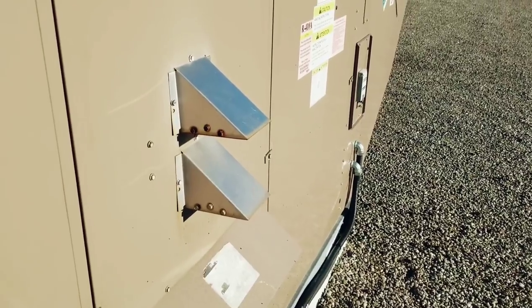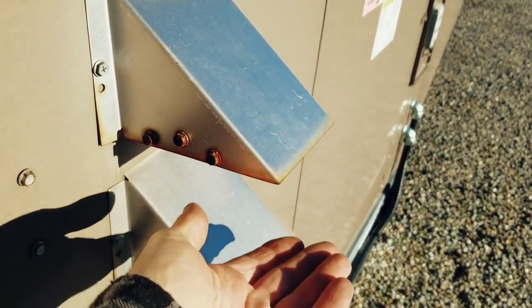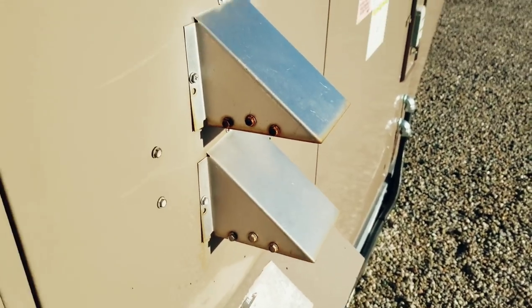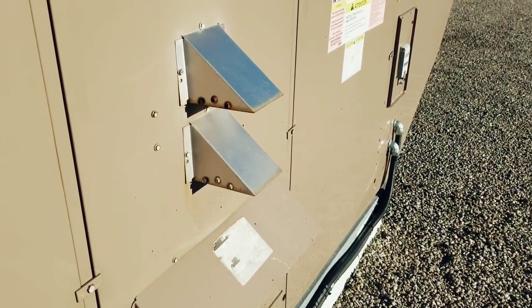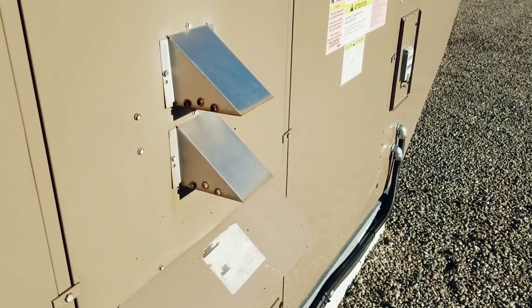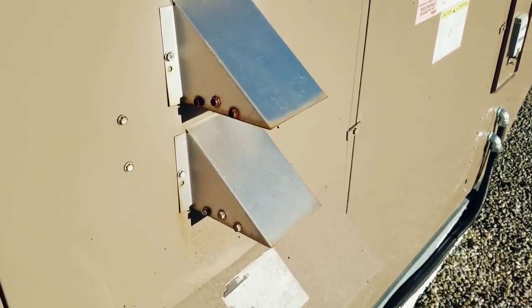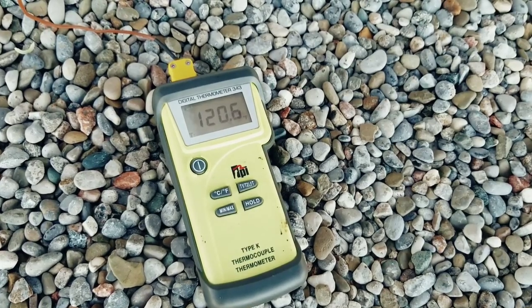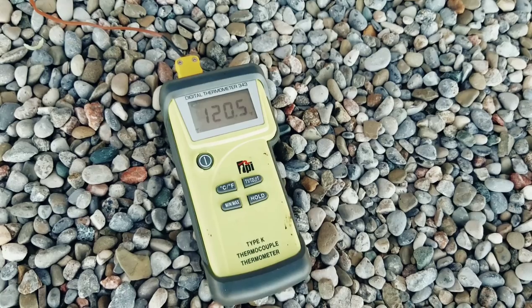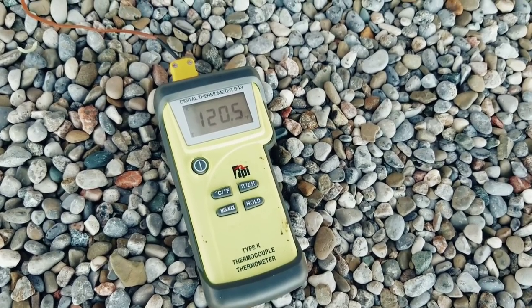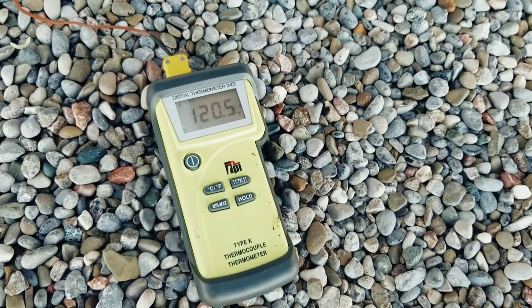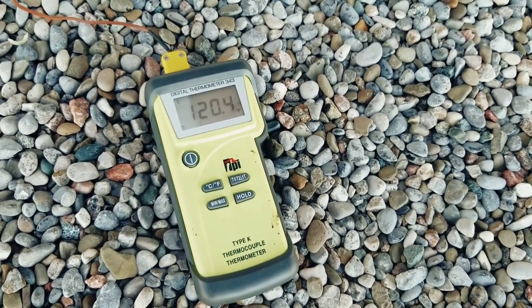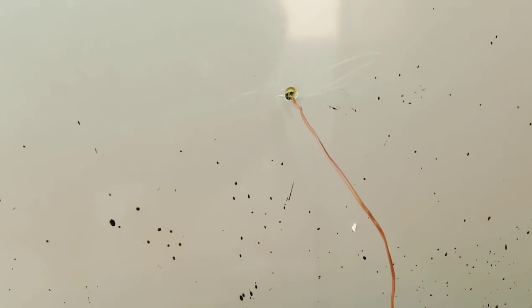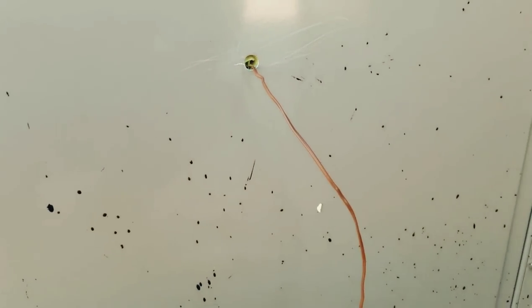Okay, right now the BAS has this unit calling for two stages of heating, and it's been running in two stage heat for about an hour and a half now, trying to get the space to about 70 degrees Fahrenheit. So at the deck, we have about 75 degree air roughly. All right, we have 120 degrees supply air, so we got about 45 degrees across that heat exchanger. There's my probe right into the door there. Supply air door. Move back so I can show you guys.